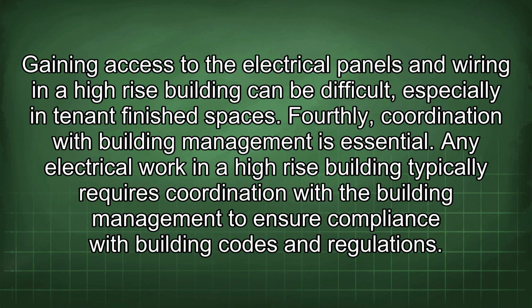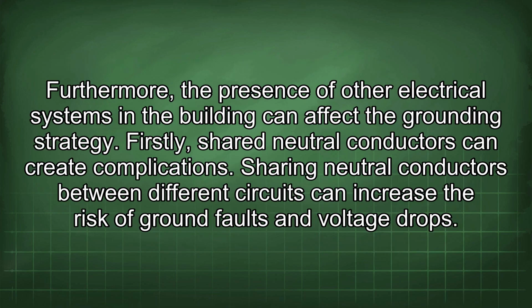Fourthly, coordination with building management is essential. Any electrical work in a high-rise building typically requires coordination with the building management to ensure compliance with building codes and regulations. Furthermore, the presence of other electrical systems in the building can affect the grounding strategy. Firstly, shared neutral conductors can create complications. Sharing neutral conductors between different circuits can increase the risk of ground faults and voltage drops.